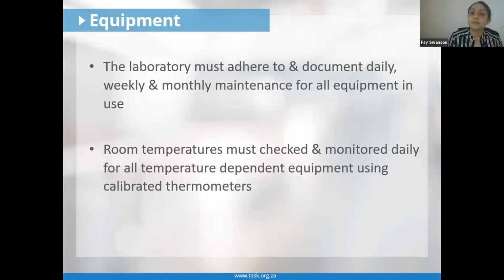Okay, again, a laboratory must adhere to and document daily, weekly, and monthly maintenance for all equipment items in use. And also the room temperature, or the room that houses the equipment pieces, particularly those that are temperature dependent. The room temperature should be monitored, and those thermometers used to monitor the temperature should also be serviced and maintained appropriately. Next slide, please.